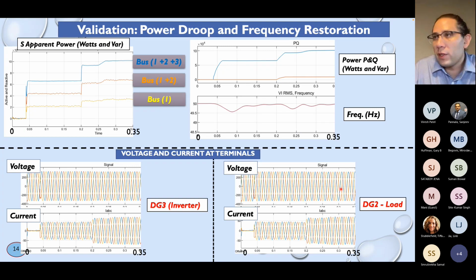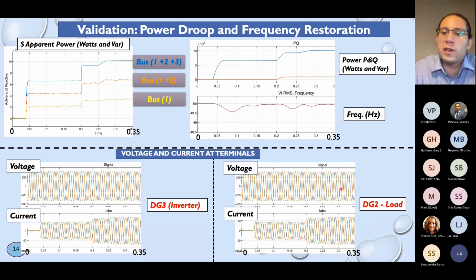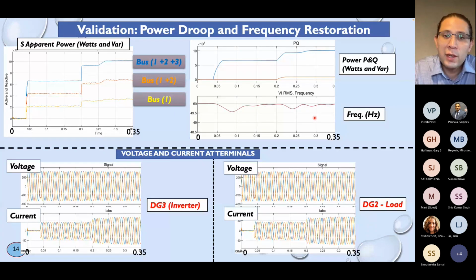For the validation process, we tested an important setting, which is the frequency and voltage. The frequency should always be maintained at nominal. In this case, we utilize 50 hertz, and the nominal is maintained thanks to the frequency restoration implemented in the inverters. We know that the frequency drops as we increase loads, as shown in the droop control model that I showed before. But with the restoration, we can keep it at nominal, which is how it is supposed to work in real life to guarantee operation of the grid within the neighborhood and keep the standards.